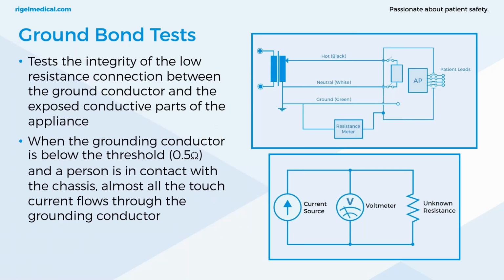So we know that Class 1 equipment has a ground conductor, so leakage current on the chassis or enclosure can flow to ground to prevent harm to anyone. Grounding is a proven safety measure for preventing electrical shock. Measuring and checking the resistance between the appliance and ground ensures that the safety measures continue to work throughout the device's lifespan or life cycle.